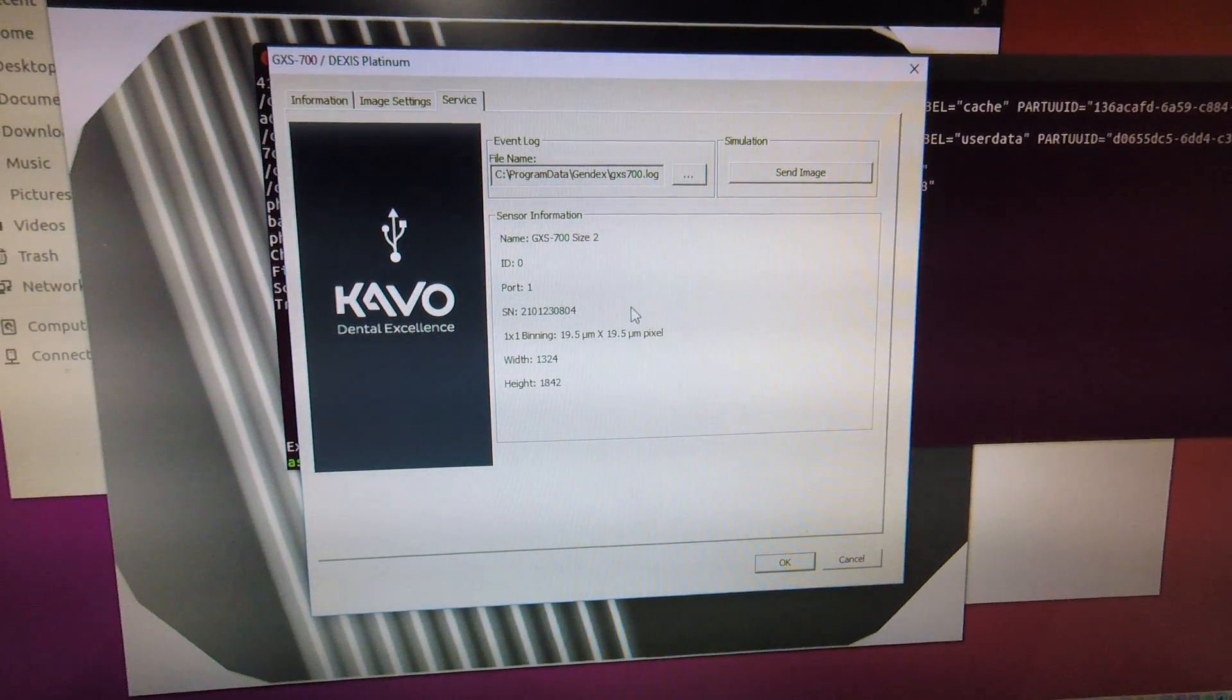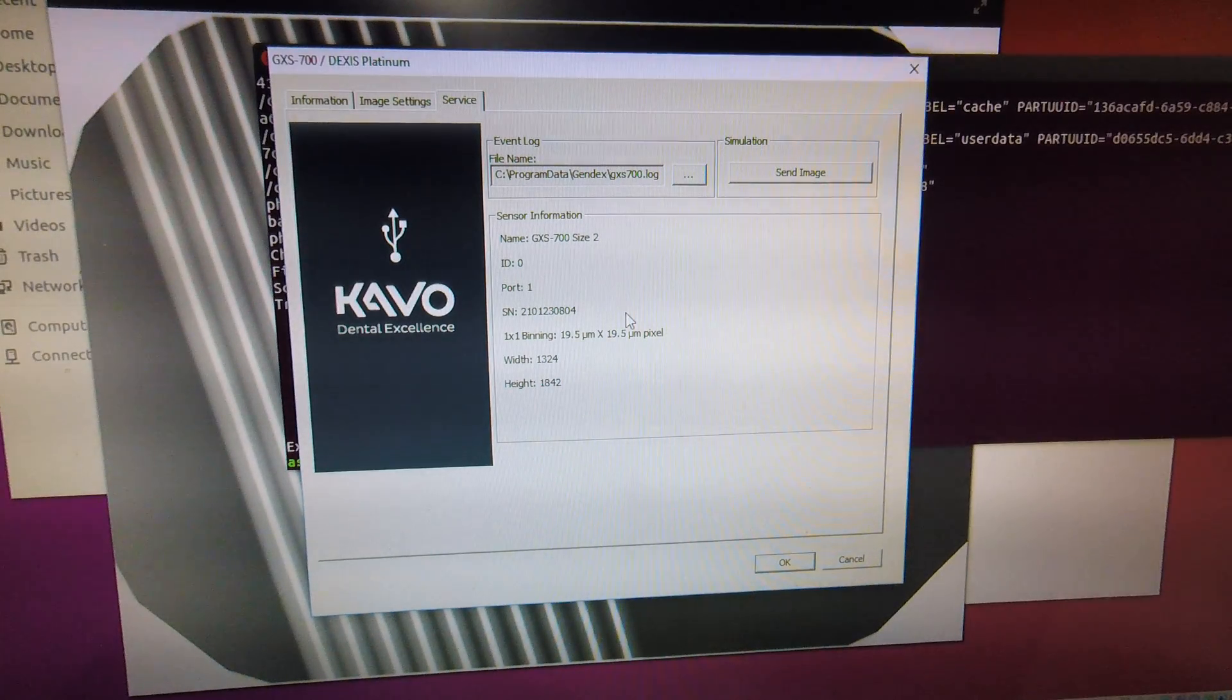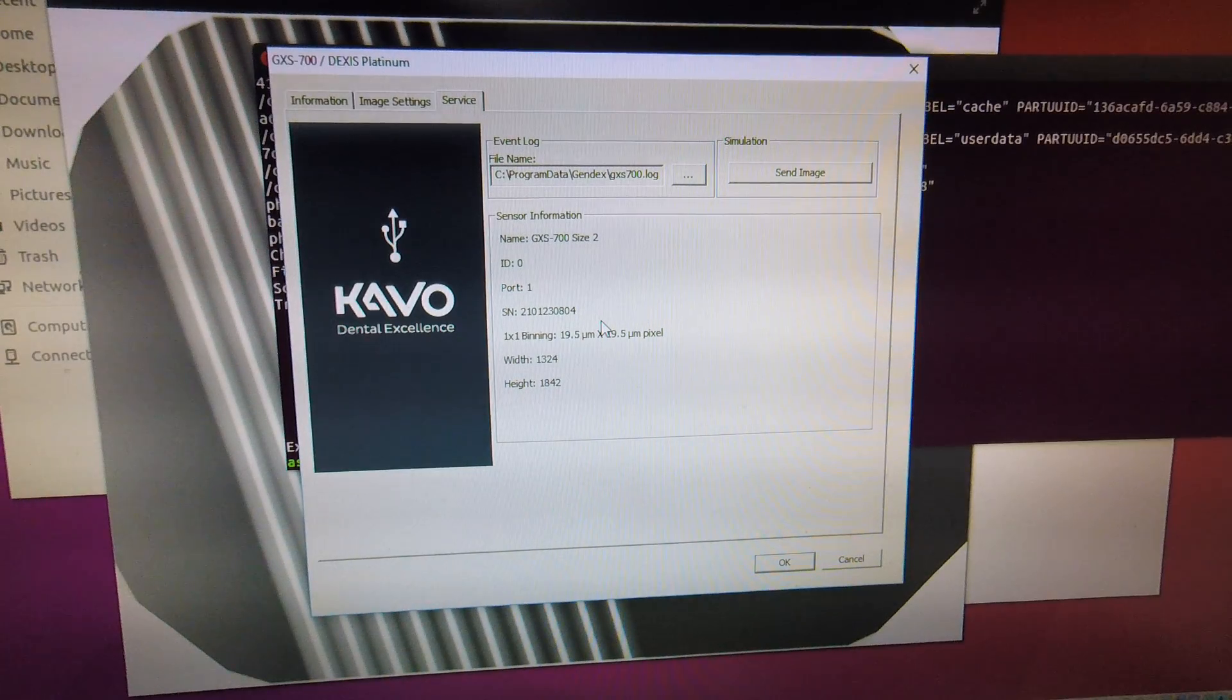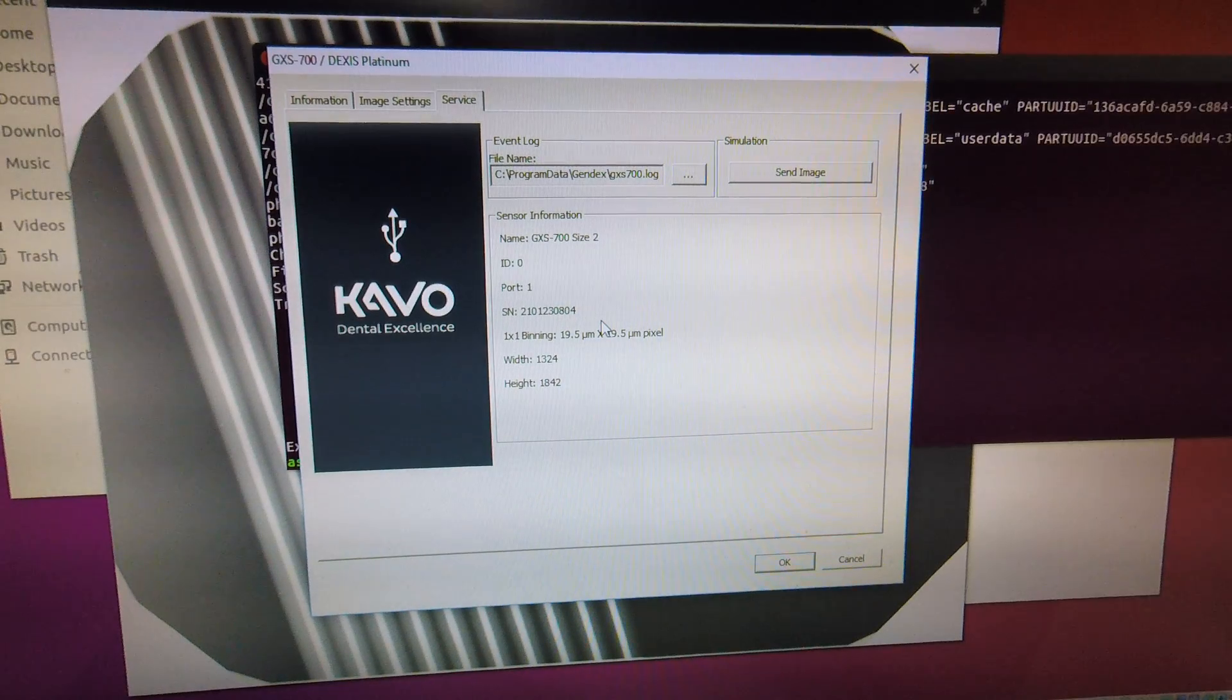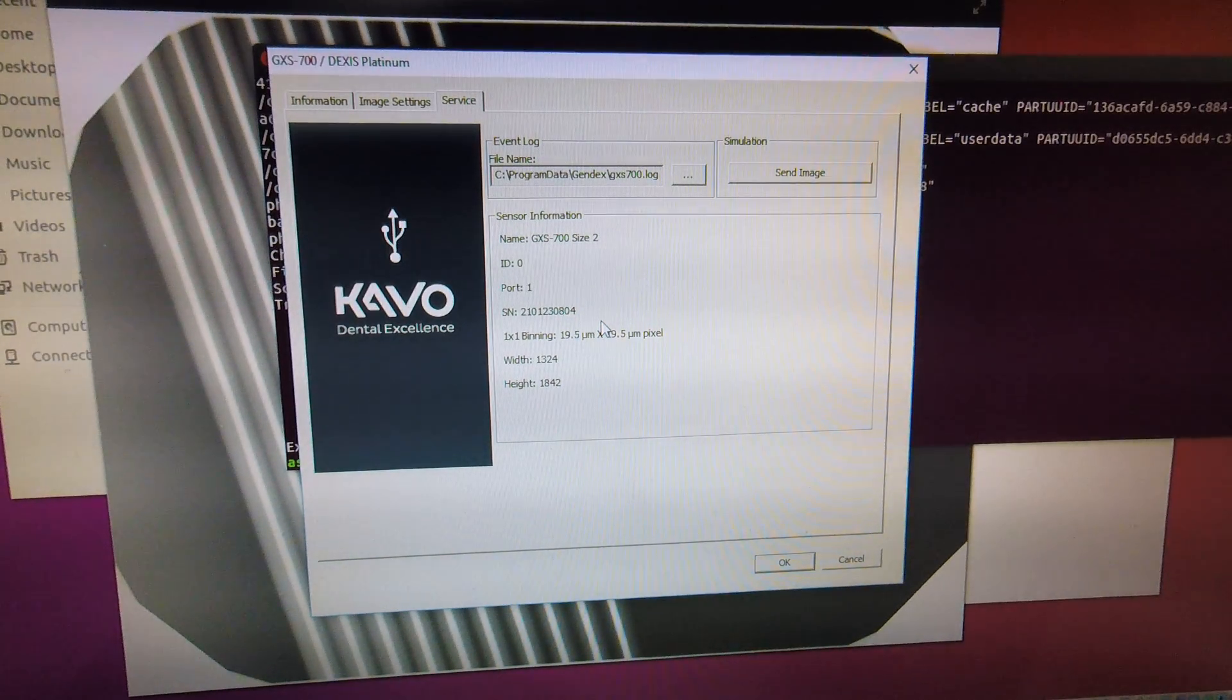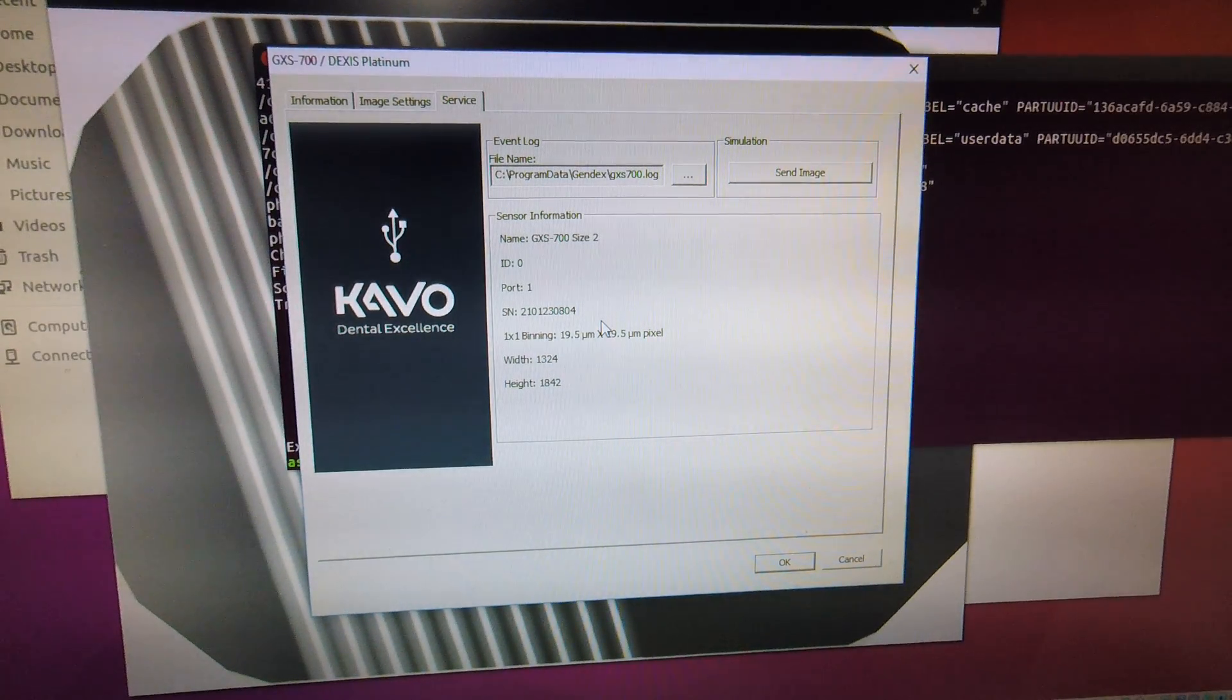Now those files are just indicated by serial number. When they are connected to the PC it just looks at the serial number. So if you have the correction files from a different sensor you can just rename them to the same sensor. It won't be the proper flat field and dark field files necessary to give you a clean picture but it will trick the sensor to be able to interface.